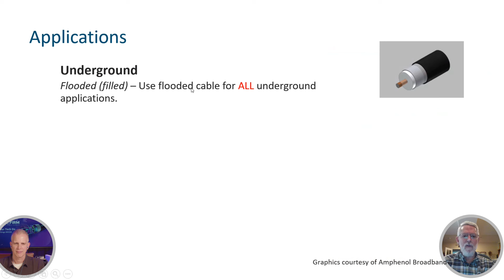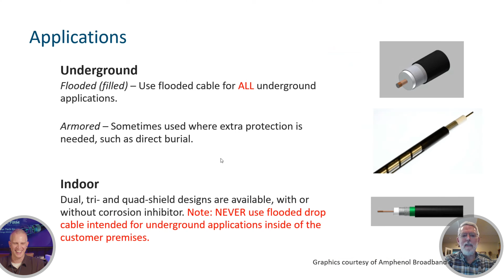Armored cable, this stuff's a bear to work with. There's a cutaway on the cable here you can see, and I think it's a stainless steel wrap around the cable. So if I remember right, a jacket is first put on the cable, then the armor goes on top of that, and there's probably flooding compound in there, then another jacket. This gives extra protection. It's good for direct burial. This stuff can cut the daylights out of your hands if you're not careful when you're cutting the cable to prepare for a connector. I have cut connectors onto this kind of cable, and it is a pain in the patootie, but it is available.